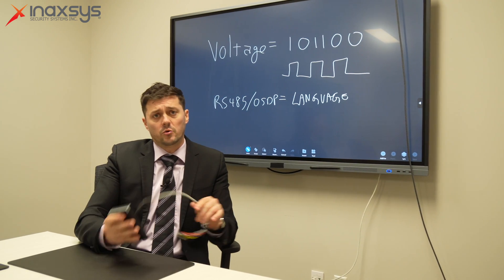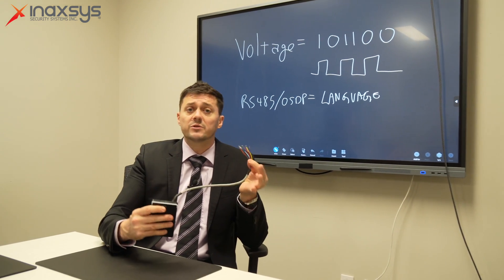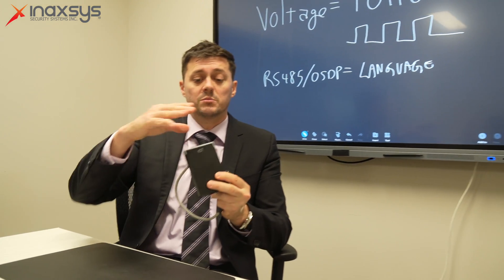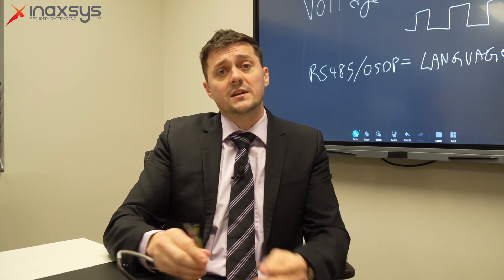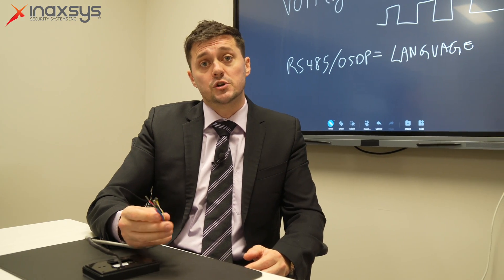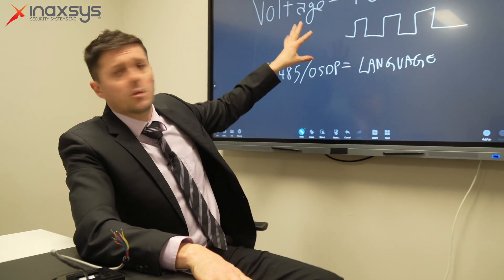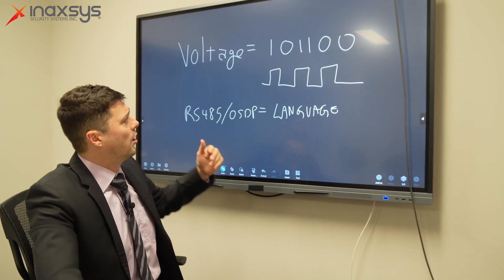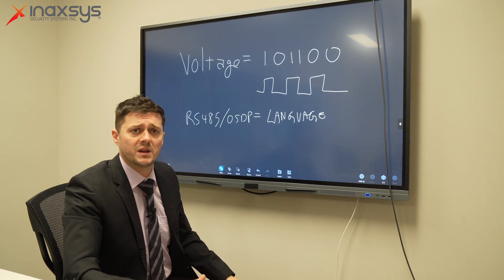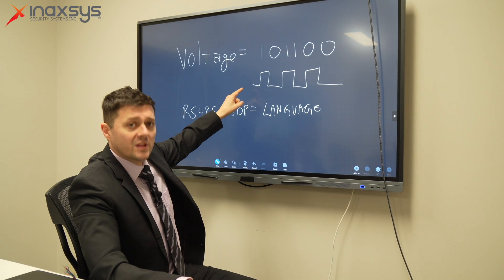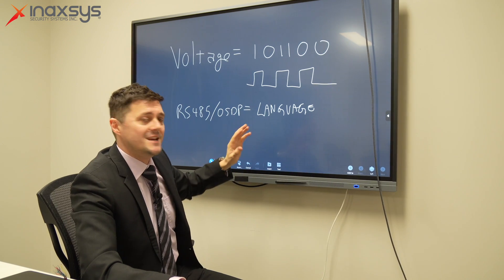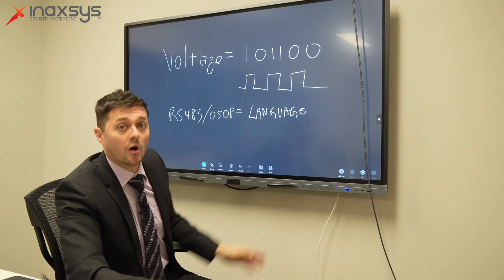Let me explain. On the back of our readers, you have multiple different cables. Wiegand technology is the language that is spoken between the reader and the controller. Wiegand is simply ones and zeros, but the ones and zeros we're talking about are voltage. What I mean by ones and zeros is, when you're looking at Wiegand — each bit, whether you have 26-bit, 32-bit, or 105-bit — by monitoring the voltage, you can actually see exactly which ones and zeros are in which position.